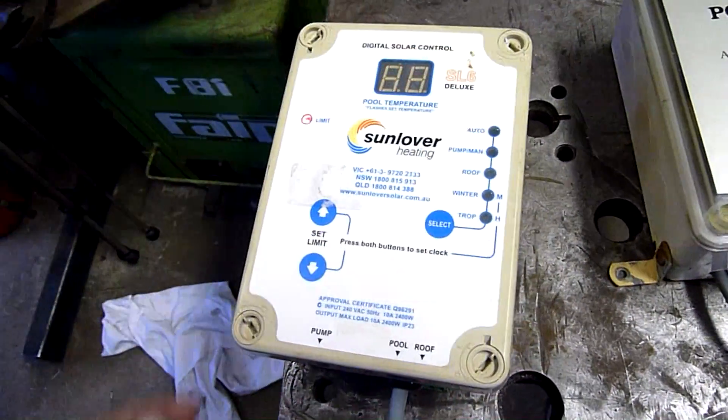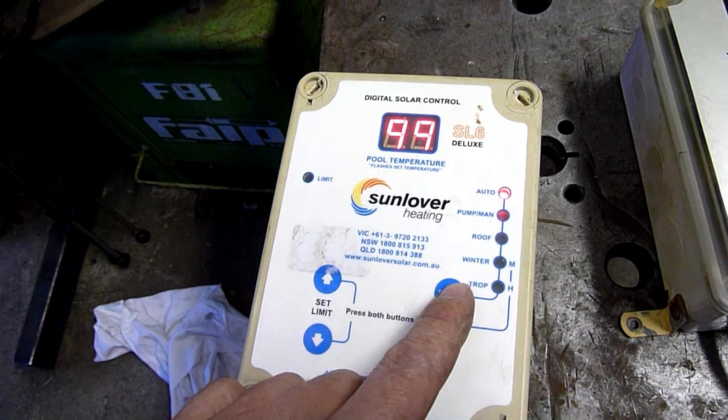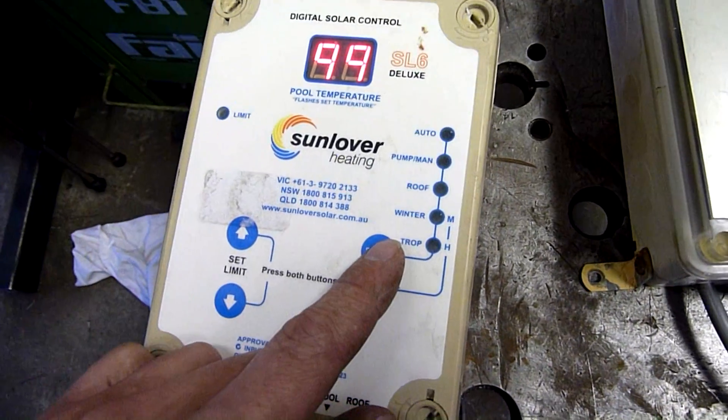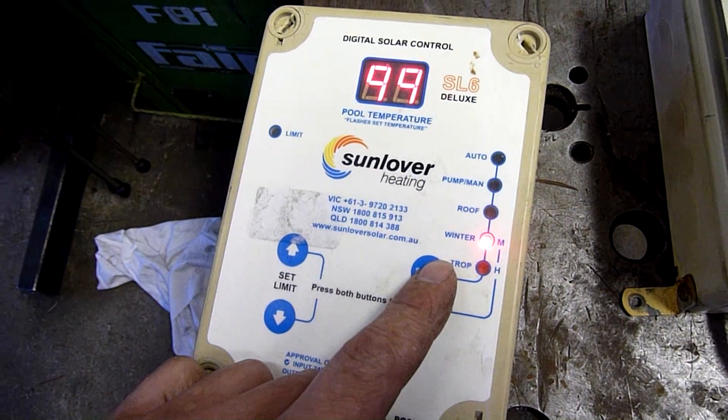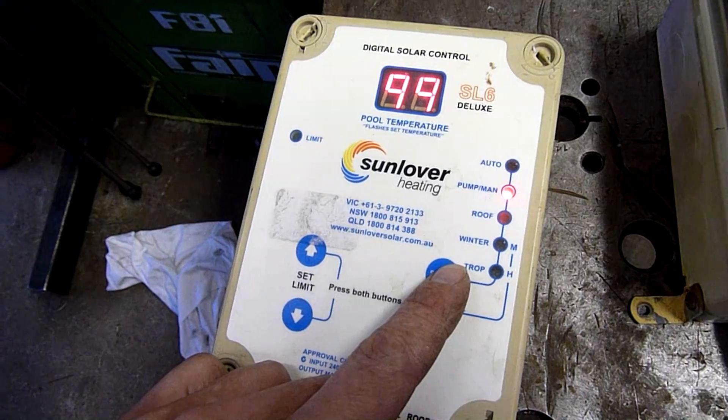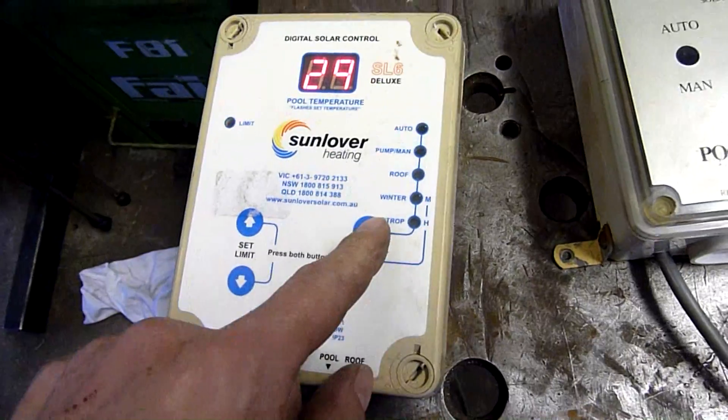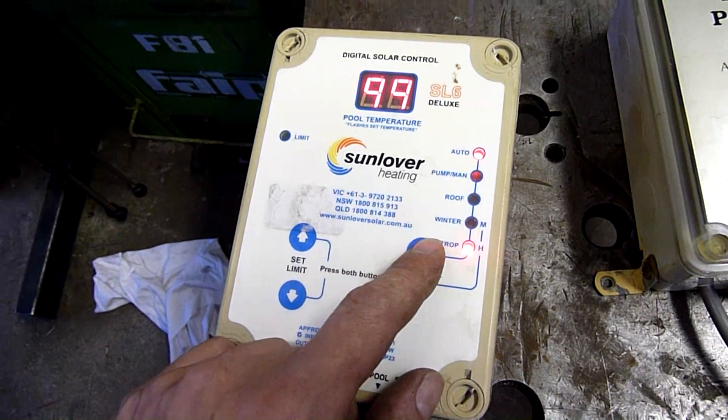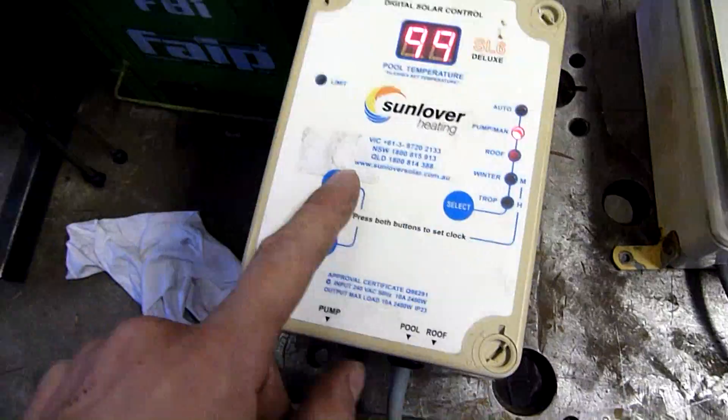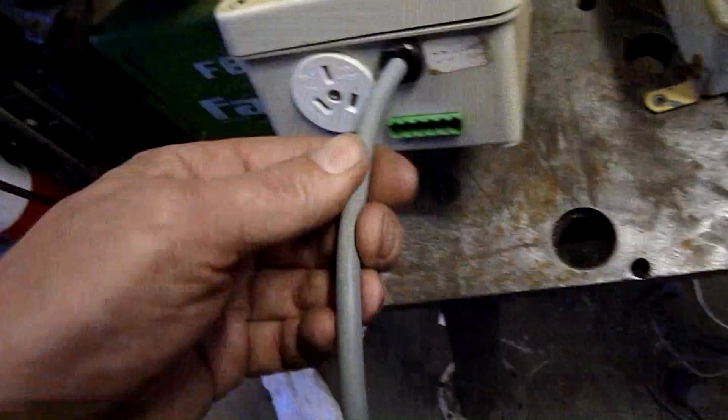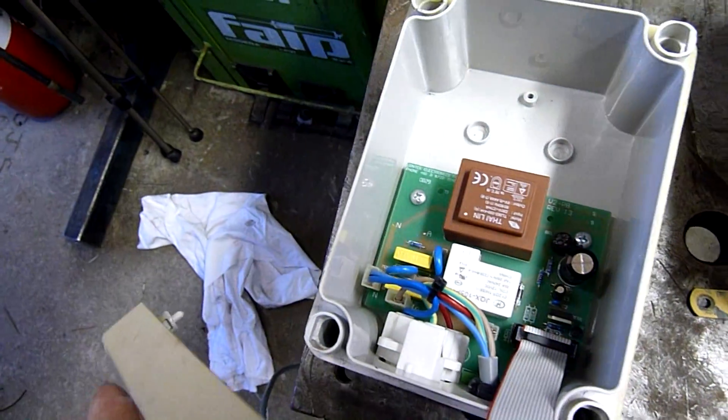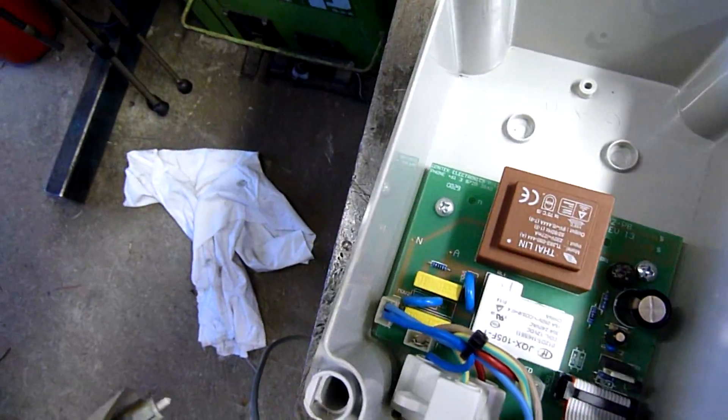Well, it seems like someone had been inside this one and unplugged the ribbon cable. That would explain why it was dead. So it's just going through its start-up sequence. Auto, pump or manual. It's not even trying to trigger the relay and pump manual. Mind you, it's throwing error code because there's no thermistors attached to it.